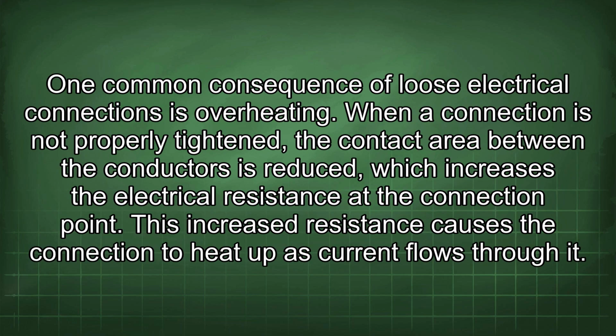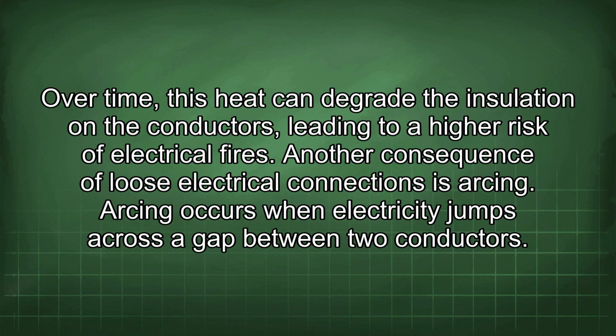One common consequence of loose electrical connections is overheating. When a connection is not properly tightened, the contact area between the conductors is reduced, which increases the electrical resistance at the connection point. This increased resistance causes the connection to heat up as current flows through it. Over time, this heat can degrade the insulation on the conductors, leading to a higher risk of electrical fires.